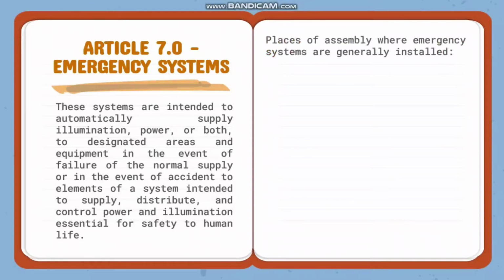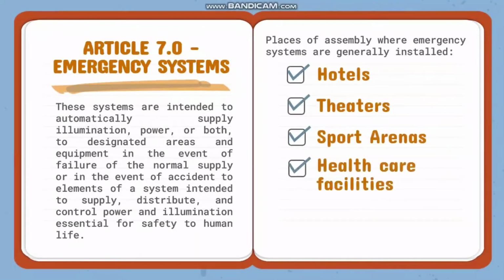Places of assembly where emergency systems are generally installed: hotels, theaters, sports arenas, healthcare facilities, and similar institutions. So emergency systems are generally installed in places of assembly or places subjected to occupancy by a large number of persons na kailangan ng artificial illumination para sa safe exiting and for panic control sa buildings in case na magkaroon ng power loss or emergency.